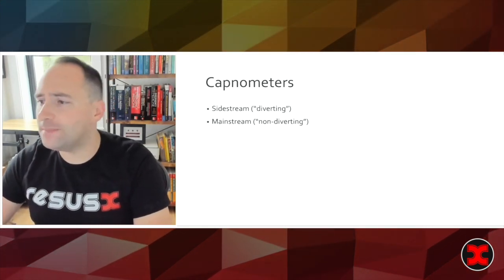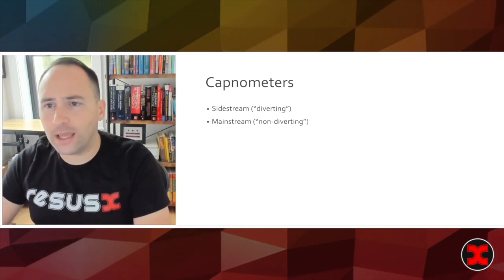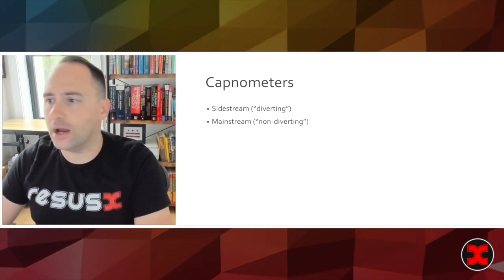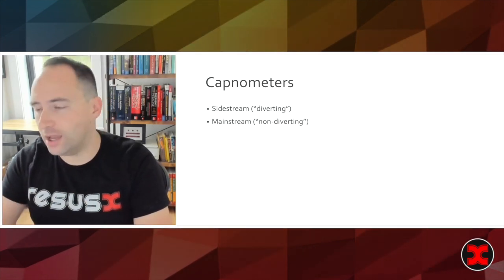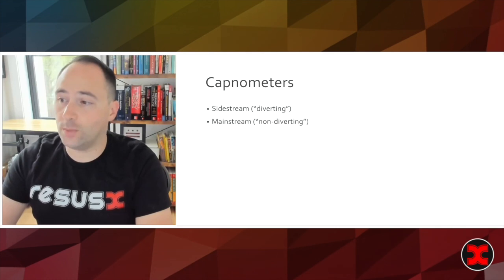So what types of capnometers exist? Well there are two in mainstream use. There is the sidestream or what you'll hear called diverting capno or mainstream which is non-diverting.